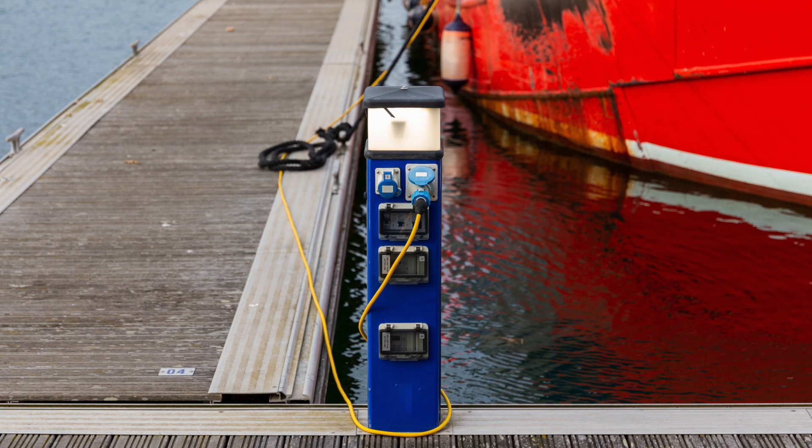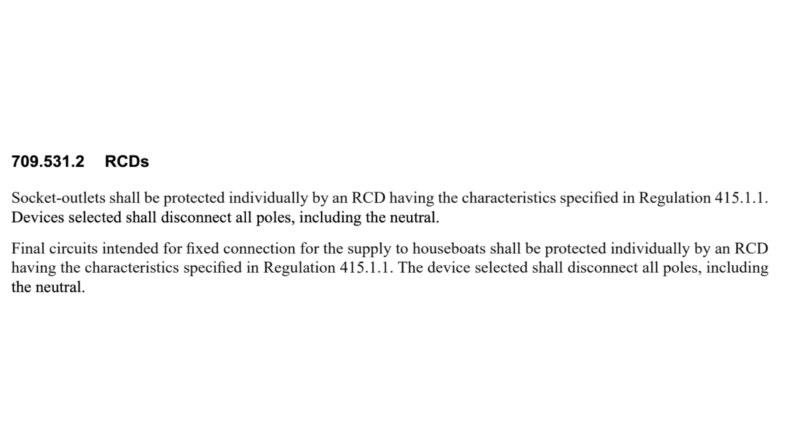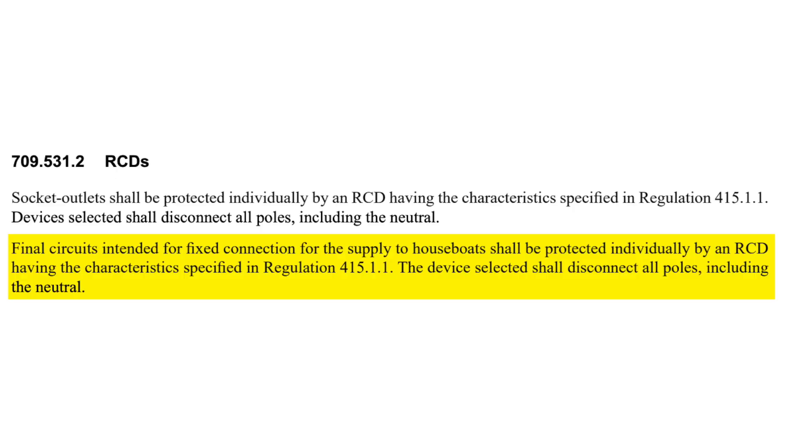The first example is marinas and similar locations. Regulation 709.531.2 says that socket outlets shall be protected individually by an RCD having the characteristics specified in 415.1.1. Devices selected shall disconnect all poles, including the neutral. Also, final circuits intended for fixed connection for the supply of houseboats shall be protected individually by an RCD having the characteristics specified in 415.1.1. Devices selected shall disconnect all poles, including the neutral.